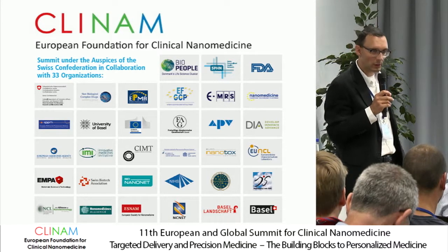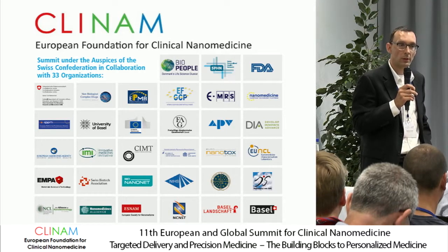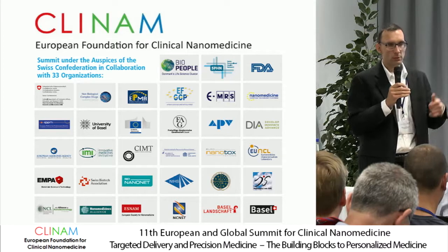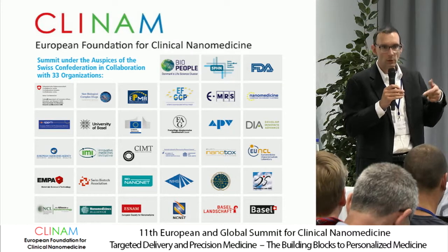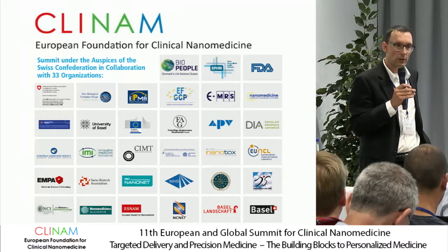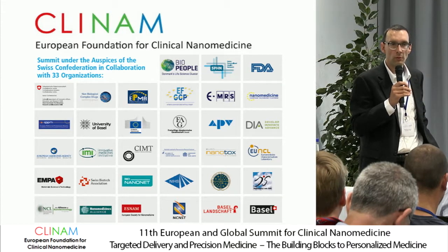So each laser has been calibrated, so we have a whole calibration set. So a whole calibration table for fluorescent mode for each wavelength of a laser and for each fluorescent mode. So this has to be taken into account. Once you want to measure concentration, you have to take into account all that.